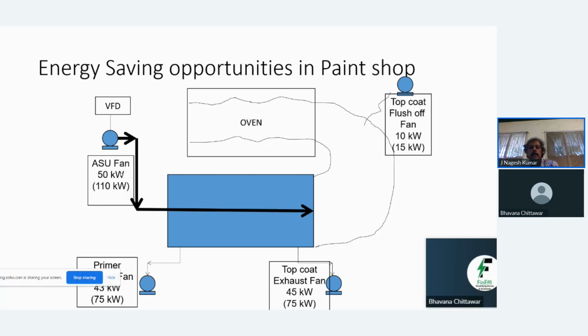As a result, we find many equipment with VFD operated at 50 hertz. When you question them why they want to operate a VFD at 50 hertz, they say it acts as a good starter. Starter, okay, but a VFD at full speed, 50 hertz, you're going to lose energy - the VFD itself will consume about 3 to 5% of the energy. So having a VFD and operating at 50 hertz doesn't make sense. This is a great opportunity. In many cases we have asked them to bypass the VFD.